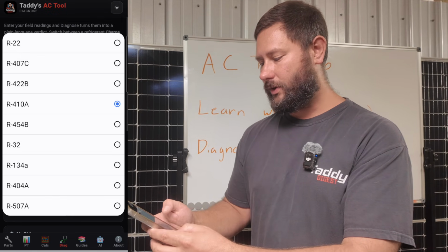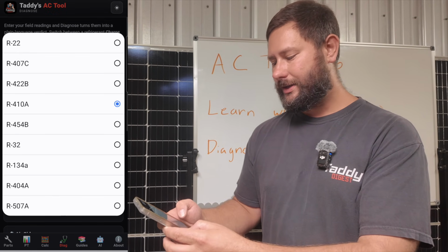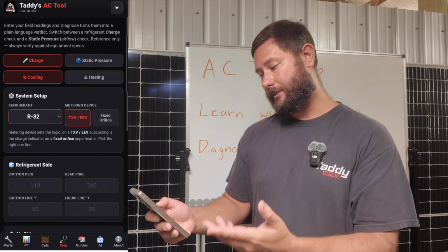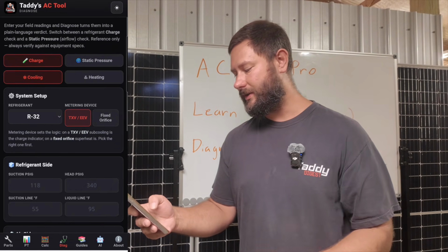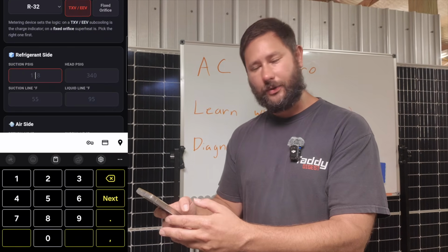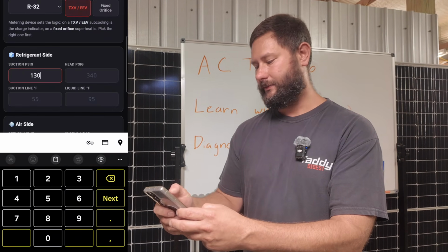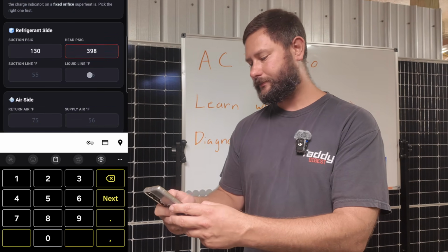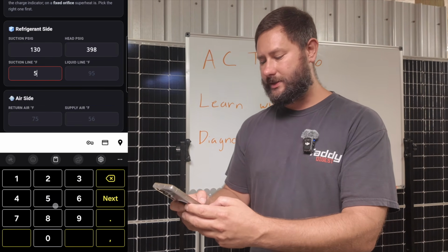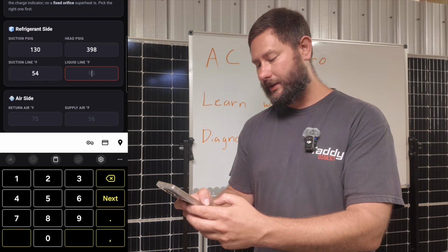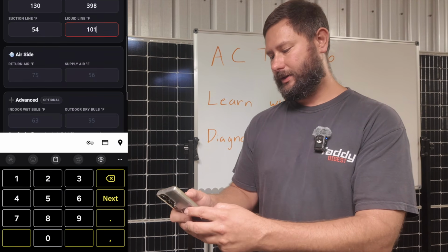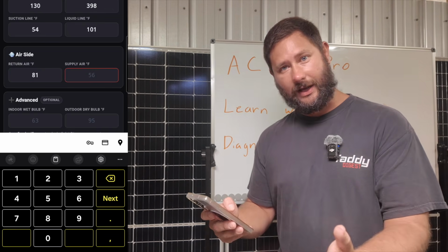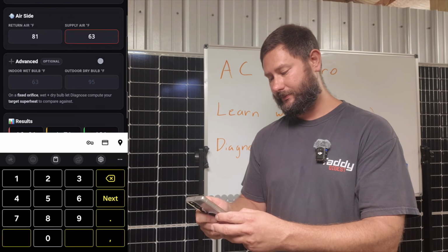So let's say we're working on a, let's choose what refrigerant, let's say R32. Let's say it can't be fixed orifice, so TXV or EEV valve. Let's say our suction pressure is 130. Head pressure is 398. Suction line, let's say it's 54. Liquid line, let's say it's 101. Return air, let's do 81. Supply air, let's do 63.